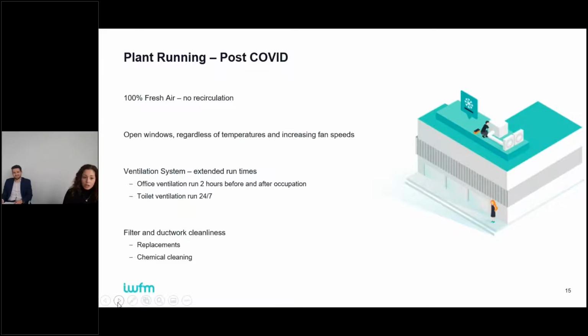First, 100% fresh air: it's recommended that ventilation-based air recirculation systems are disabled, so 100% fresh air enters the building, and air from within the premises is extracted straight into the atmosphere rather than recirculated back into the office. The belief - neither proven nor disproven - is that recirculated air can contain particulate matter, potentially the COVID strain, even after going through the filter process again, which could contaminate the area. Of course, the issue with not recirculating air is that it increases energy consumption and costs.